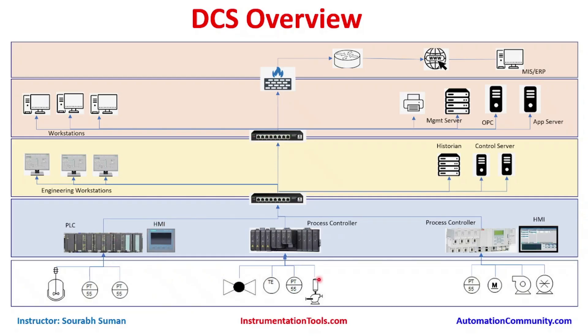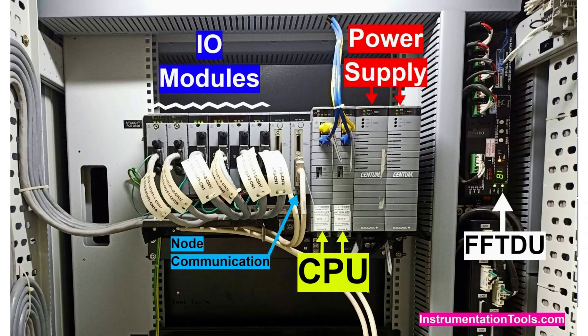These communications do not necessarily happen over TCP/IP. It could be a proprietary protocol, Modbus, DNP3, or IEC 61850 — it depends on the fieldbus protocols used. The protocol between IO cards and field instrumentation can be different, but at the upper levels of the DCS, TCP communication is quite common.